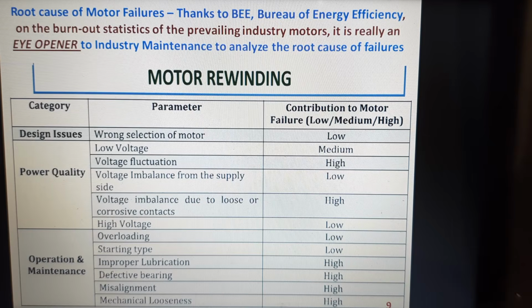You can see the category-wise breakdown: motor design, power quality, or operation and maintenance of the motor. The contribution to motor failure is high in only a few cases. Let us say voltage fluctuation or voltage imbalance due to loose or corrosive contacts, this is a high contribution. And then, operation and maintenance wise, improper lubrication, defective bearing, misalignment and mechanical looseness cause a high contribution towards motor failure. So you look into these aspects when you are anticipating any motor failure or asking why rewinding is happening. These are all the areas to be addressed now.